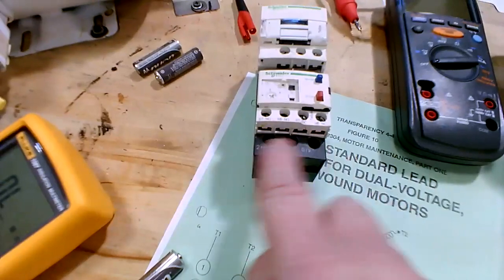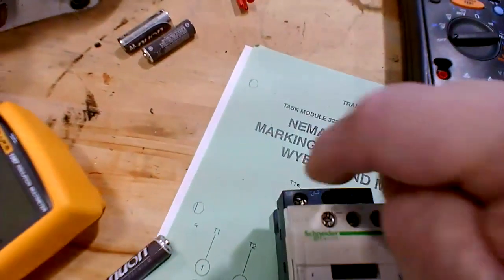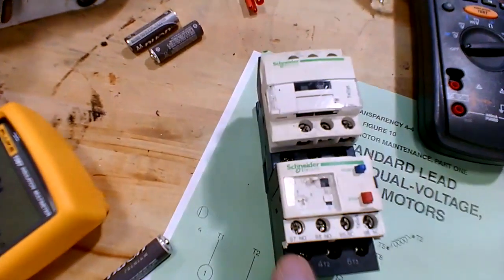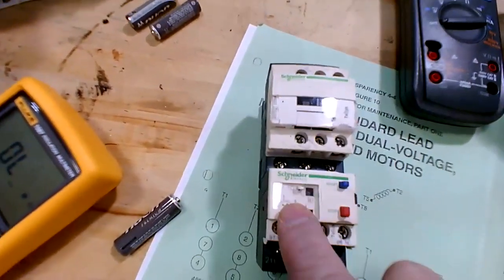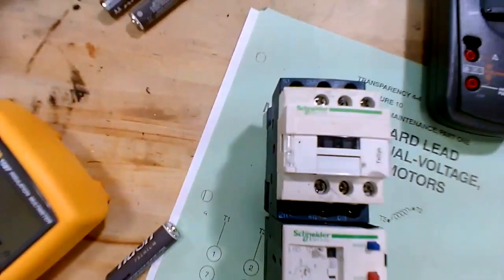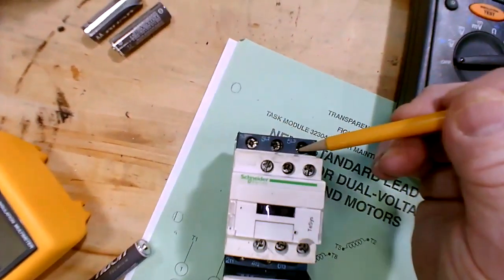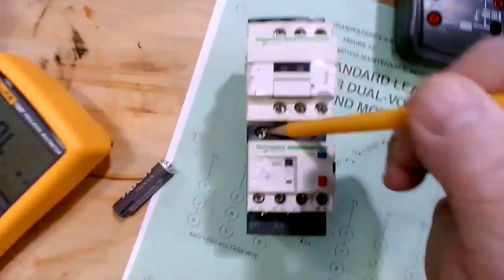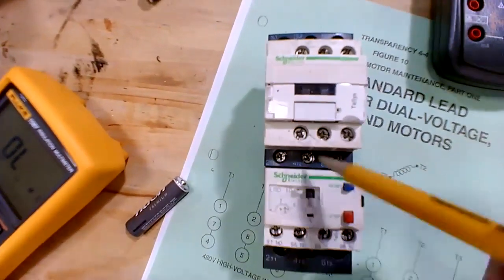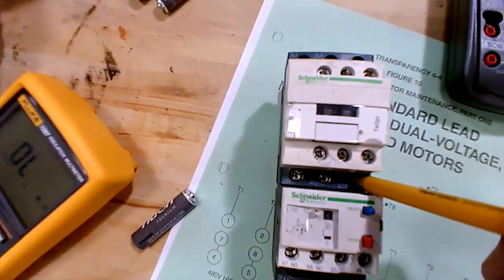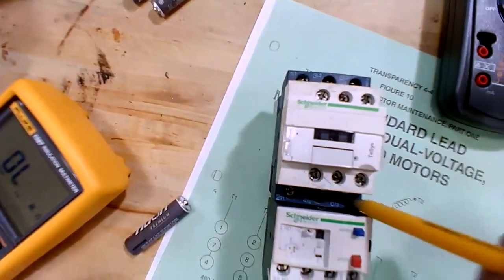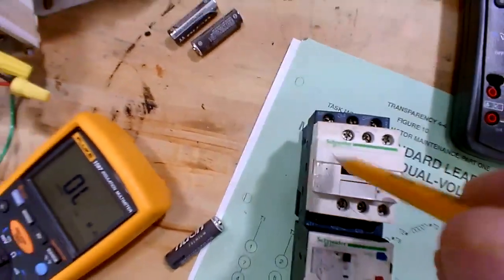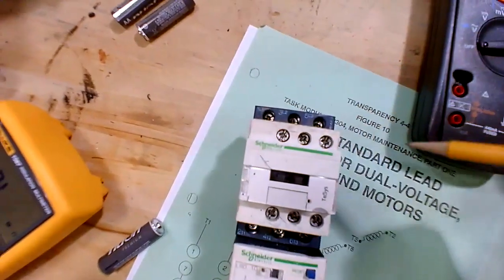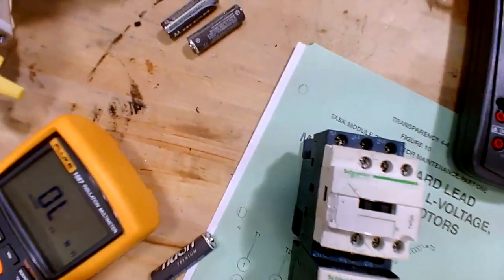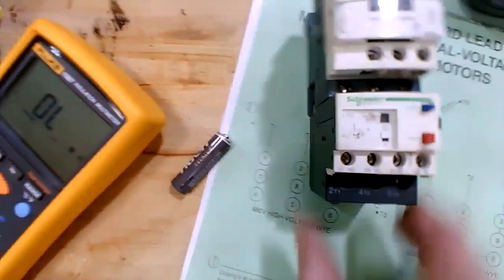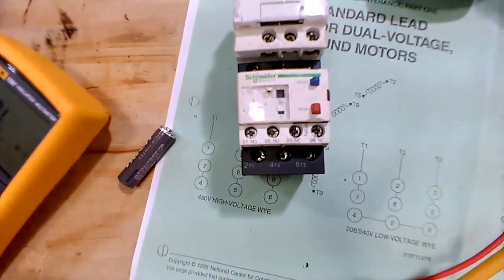If the voltages are not balanced, if you've got a weak leg, you've got to go on top and check them. So if they all look good here, and you've got a weak leg down here, it's either the overload relay going bad or one of the contacts going bad. Then you can go in between. If 1, 2, 3 read good here and you get, say, a bad leg down here, go in between them, to where the contact joins with the overload, and probe it and check 1, 2, 3 between. If it reads good, good, good, bad, good, good, bad, good, good, it's going to be the contact. But if it reads all good, bad, good, good, it's going to be a bad leg in the overload relay. Then you replace just the bottom. That makes sense? Okay, good.